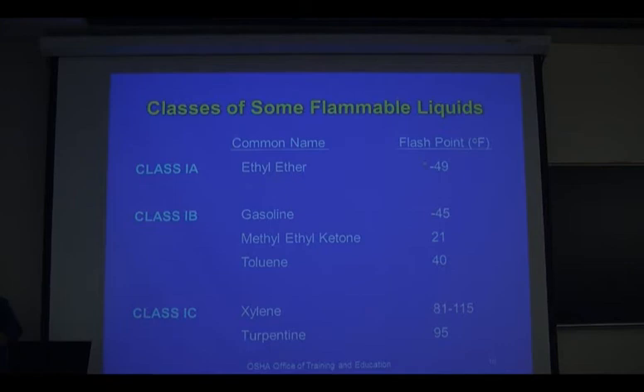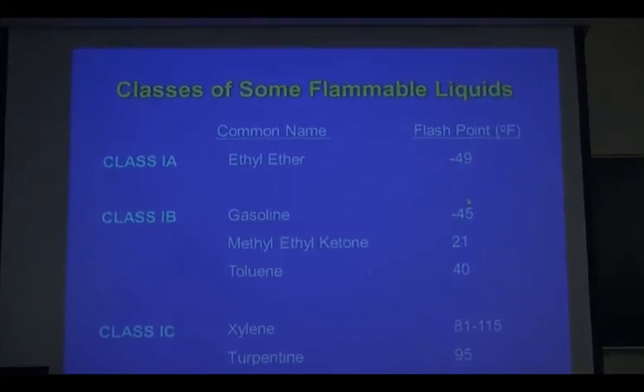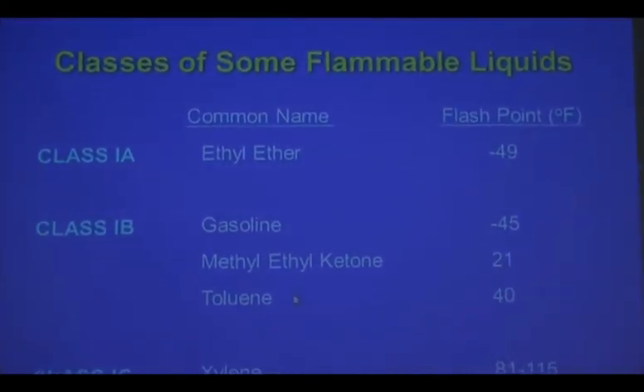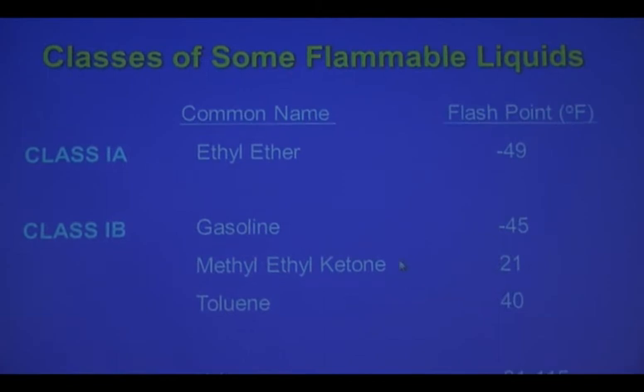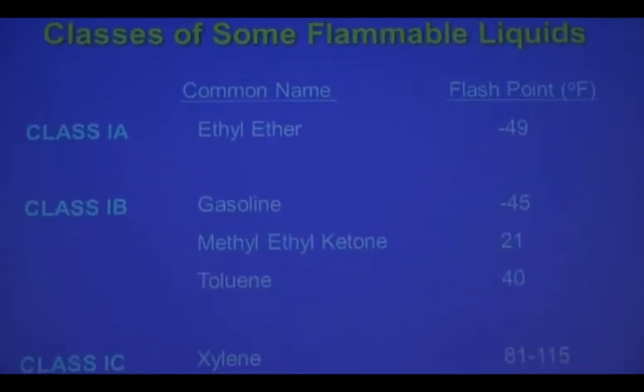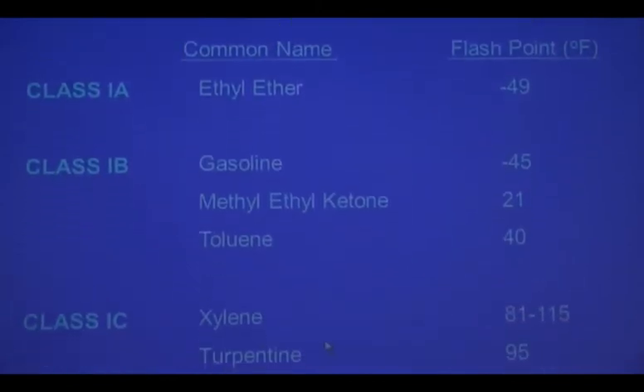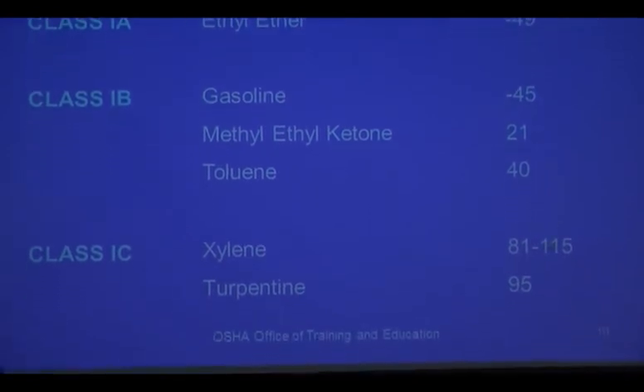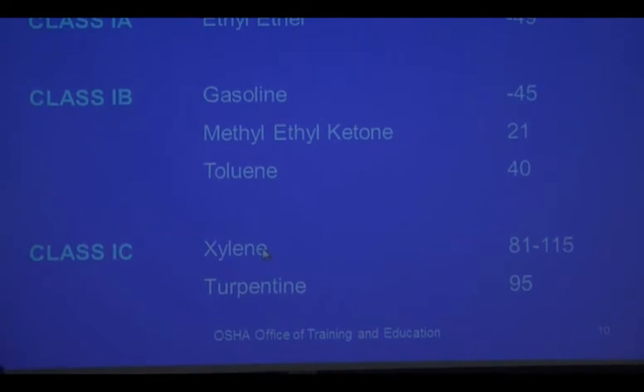Class 1A example: ether, with a flashpoint of negative 49 degrees Fahrenheit. Class 1B: gasoline, negative 45 degrees, plus a couple of others. Class 1C: turpentine, at 95 degrees — you've probably all used turpentine. So those are examples of Class 1A, 1B, and 1C.